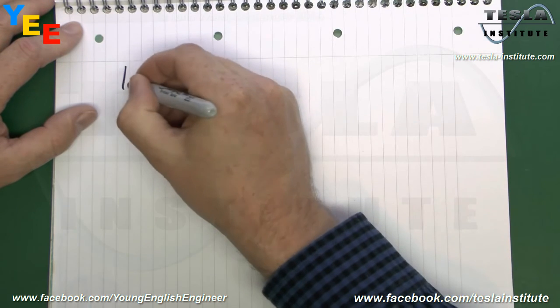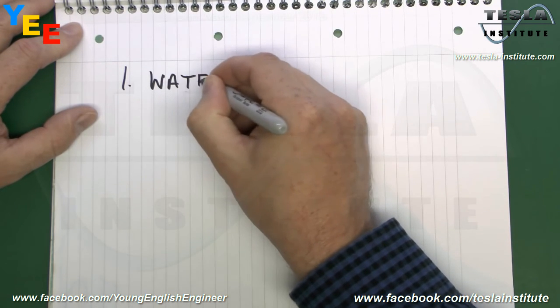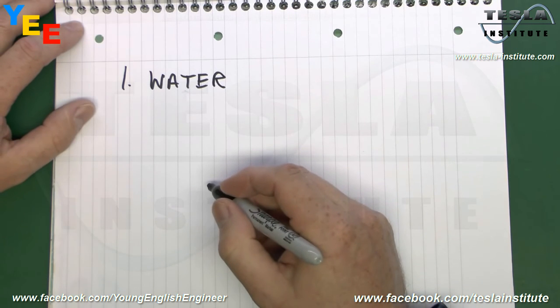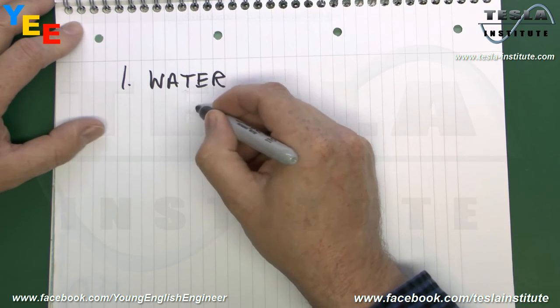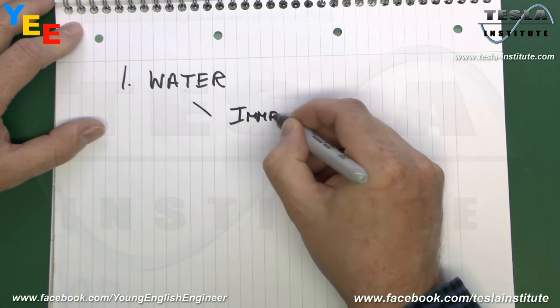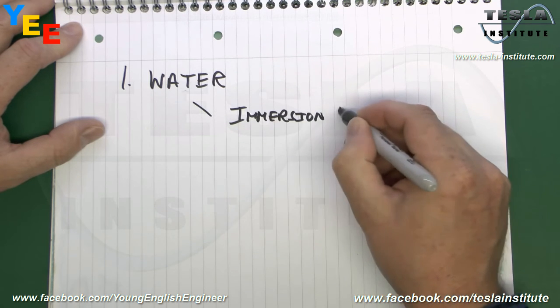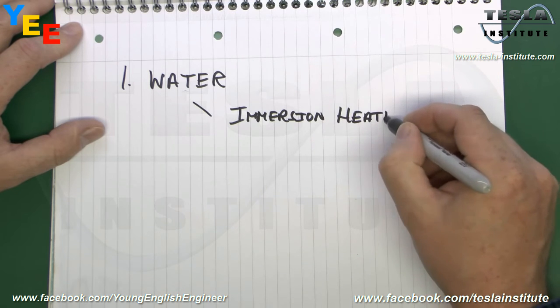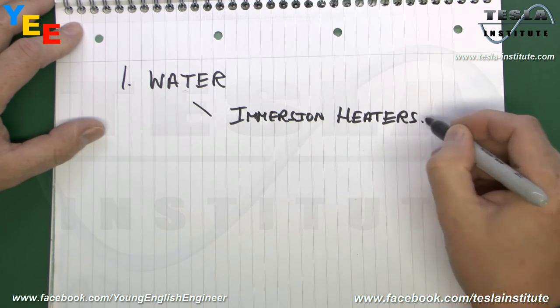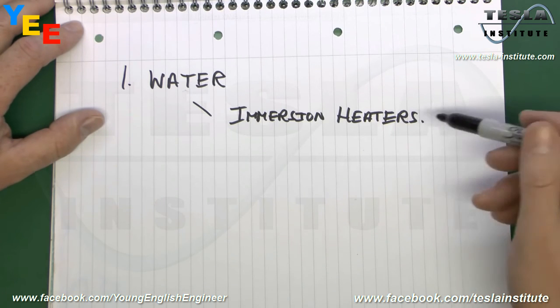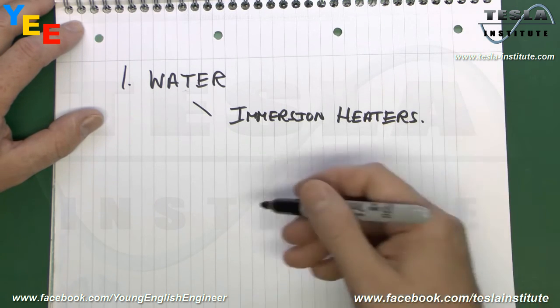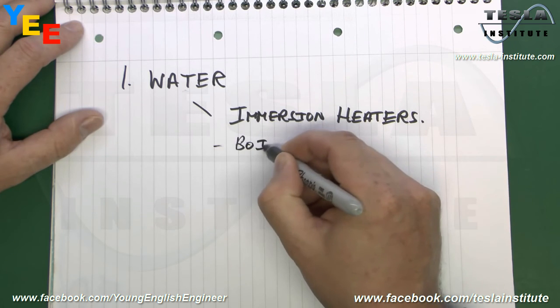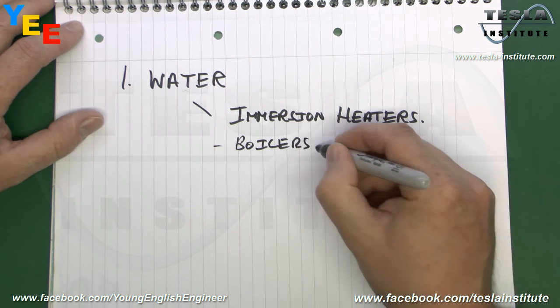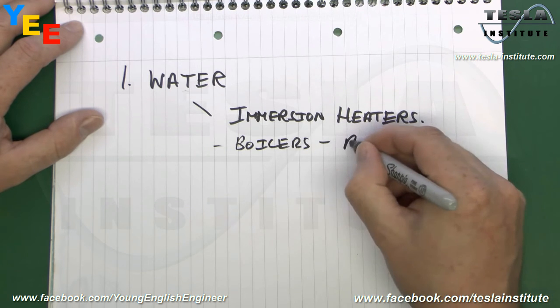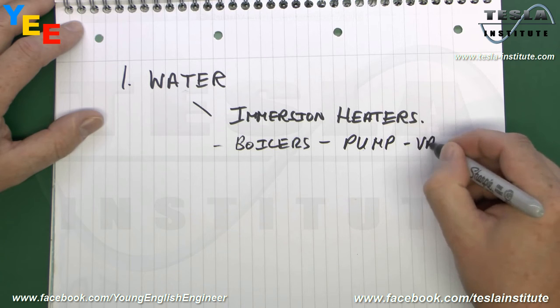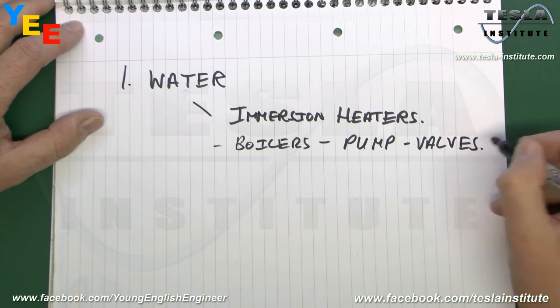And the number one item is things which contain water, or things that could be in contact with water. So common things that can go wrong are immersion heaters, being immersed in a big vessel full of water. Of course, they can corrode and fail, and the top can leak as well, so water can leak out in there. And the same thing goes for boilers, as for your central heating, and that can include all the parts of that system, so the boiler, the pump, possibly some of the motorised valves and other components of that.